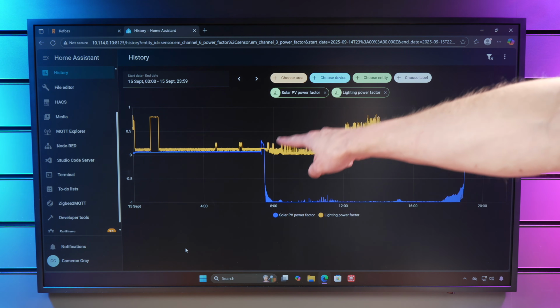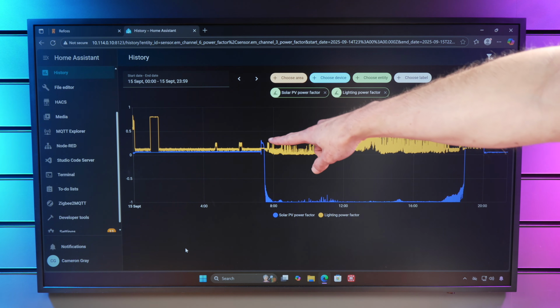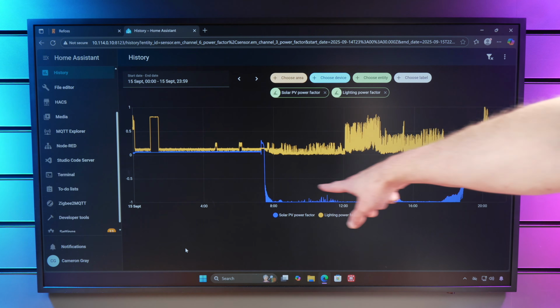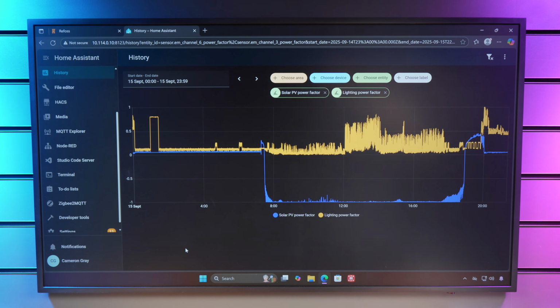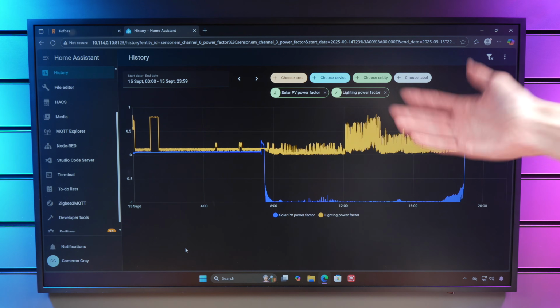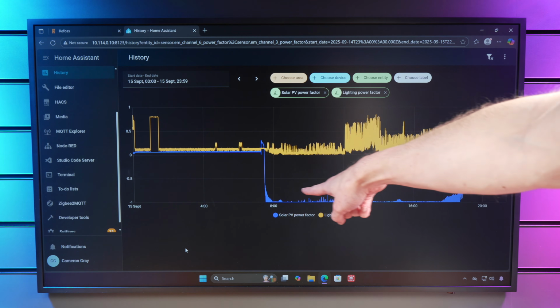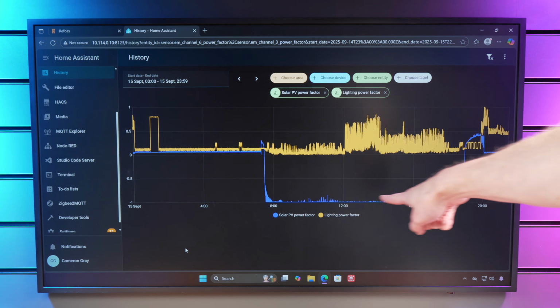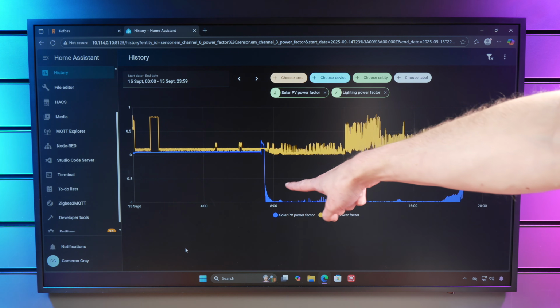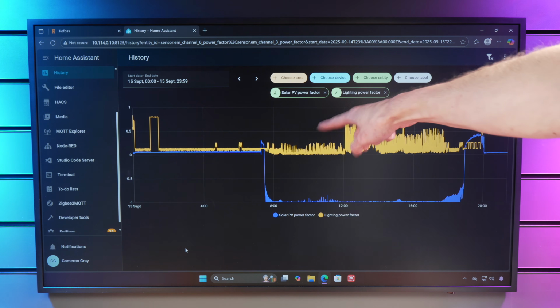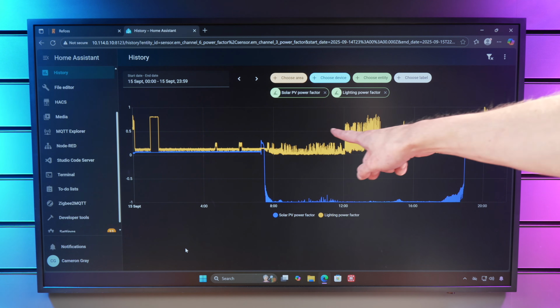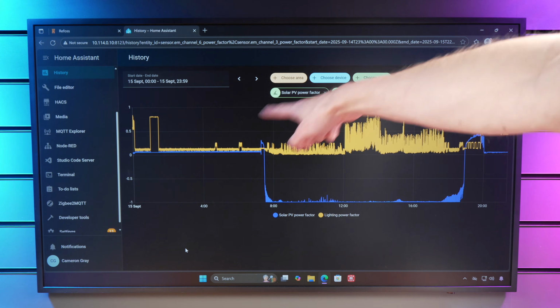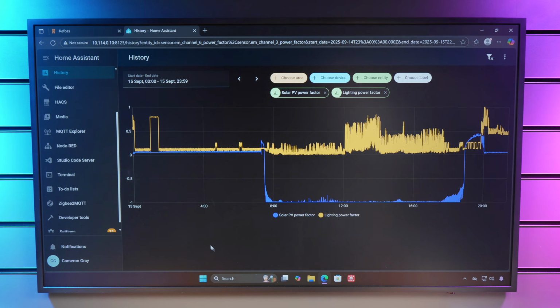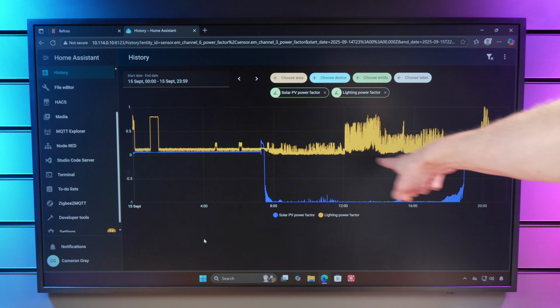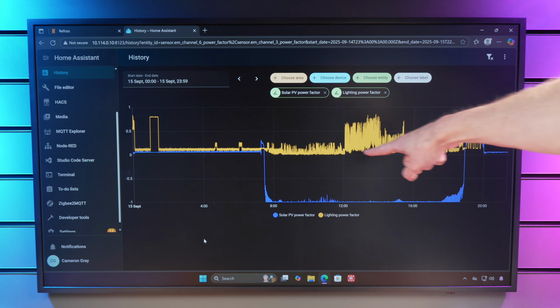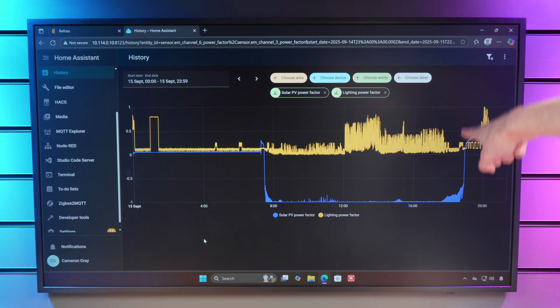But now look what happens as soon as the solar starts generating. The solar jumps down to a power factor of -1, which is what you'd expect. You're exporting power to the grid, so the power factor goes negative, and you get a power factor of -1 the entire day while the solar is generating. As soon as that happened, the power factor on the lighting circuit started fluctuating much more. There wasn't really any change in us turning lights on and off here, but as the solar was being generated, the power factor started fluctuating significantly more on the lighting circuit.